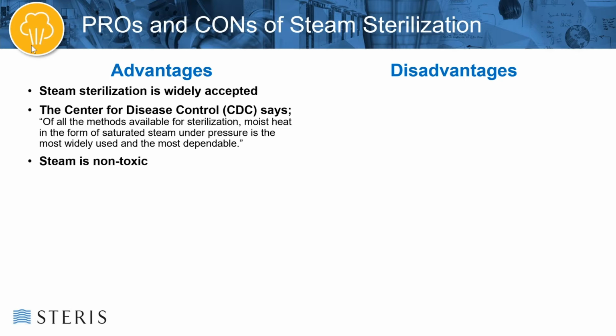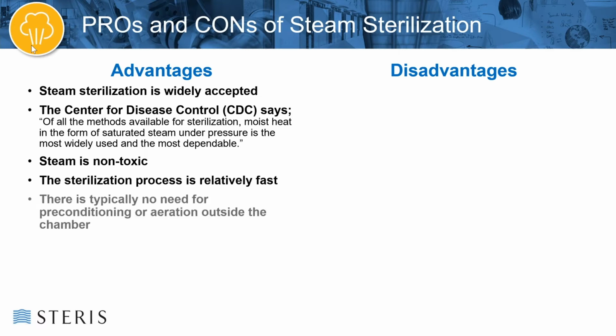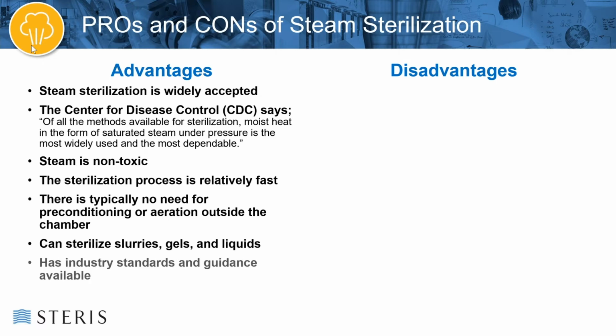Steam, of course, is non-toxic. It's simply superheated water. The sterilization process is relatively fast when compared to some of the other technologies. There typically is no need for preconditioning or aeration to occur outside the chamber. You can sterilize slurries, gels, and liquids, which quite often cannot be processed in some of the other technologies. Steam sterilization has industry guidance and standards available, which comes in very handy. And the sterilization process is well understood.